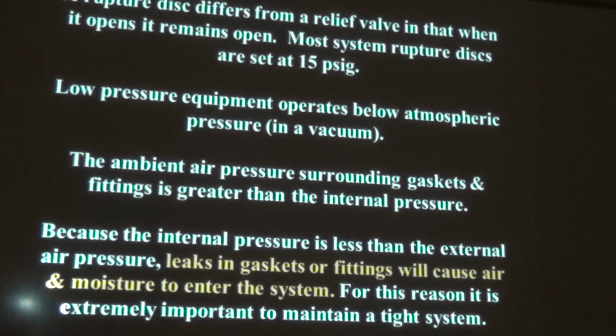Low pressure equipment using 123 especially operates below atmospheric pressure in a vacuum. So the suction side of a chiller using R123 is in inches of vacuum. The outside air pressure surrounding gaskets and fittings is greater than the internal pressure. Because chillers are operating in a vacuum, instead of having a leak pushing out, where you can see the little soap bubbles bubble out, stuff comes in, gets pulled in.